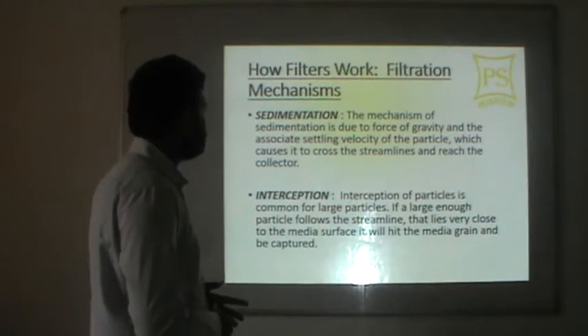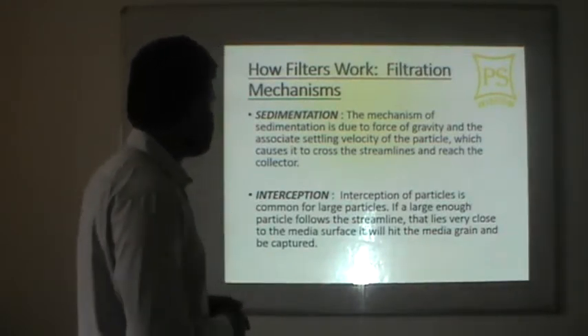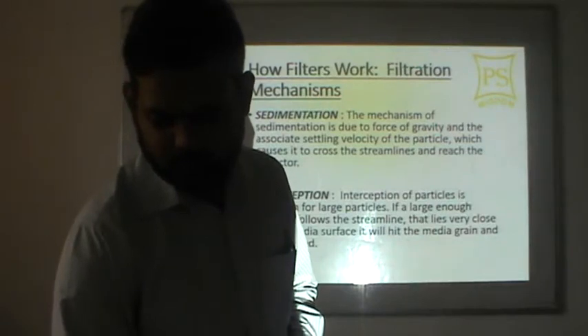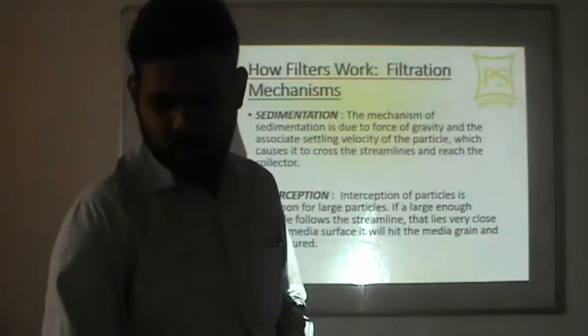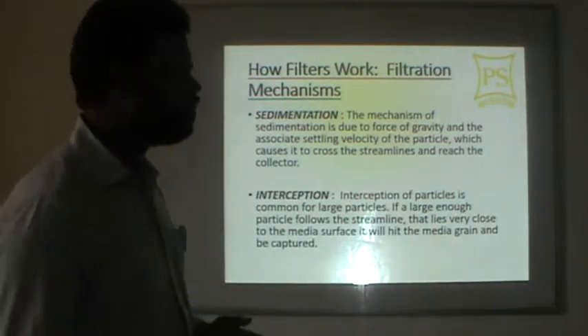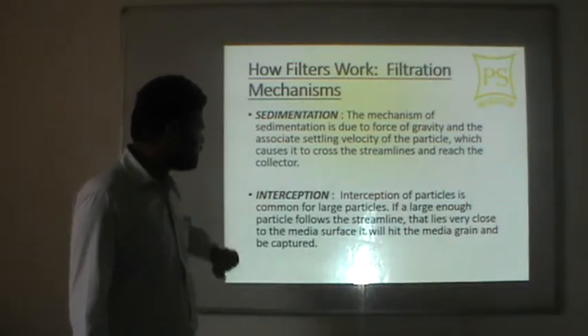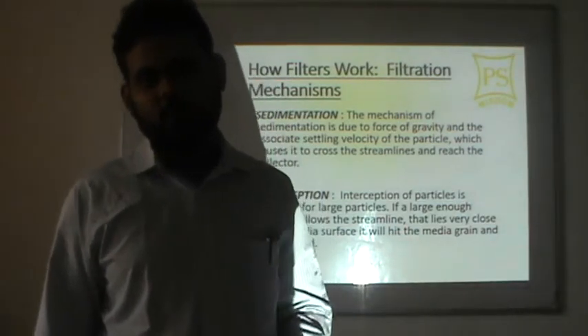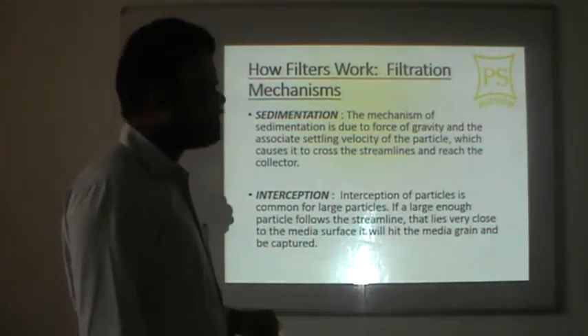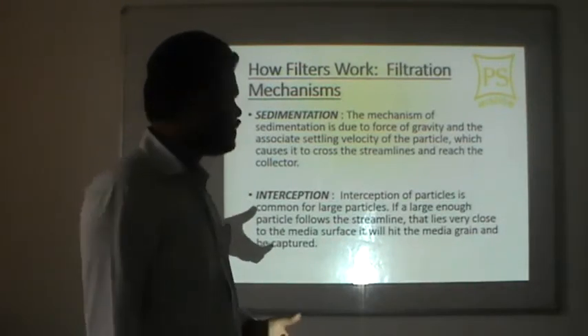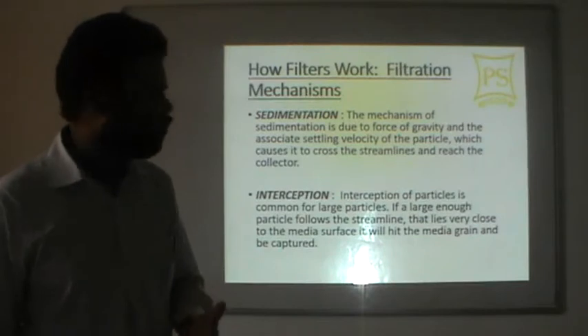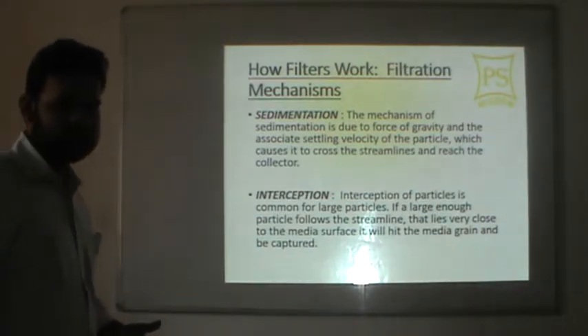The four filtration mechanisms are: sedimentation, interception, Brownian diffusion, and inertia. In the sedimentation mechanism, the force of gravity and the associated settling velocity of particles causes them to cross streamlines and reach the collector. In the interception mechanism, large particles following a streamline that lies very close to the media surface will hit the media grain and be captured.